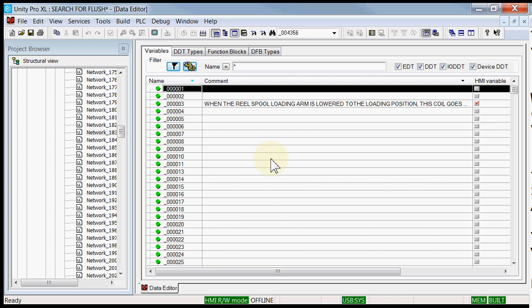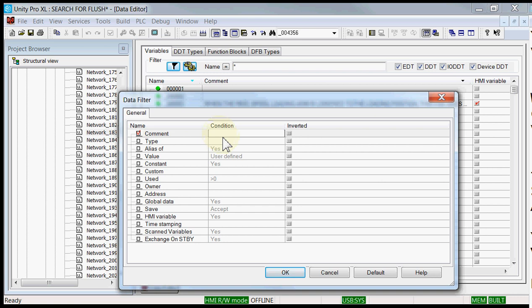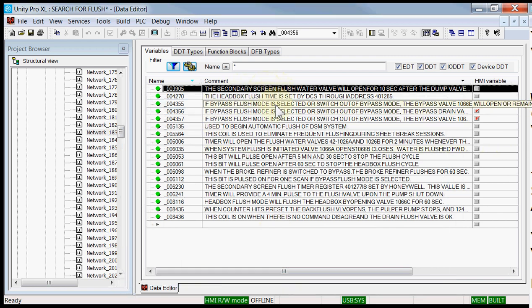From the variable editor, I want to search for all variables with the word FLUSH in the comment field — I'm looking for the bypass drain valve. So I will simply select the data filter, select the comment field, and put a condition of wildcard FLUSH in the comment field. And I will say OK. Here are all the variables with the word FLUSH in the comment.